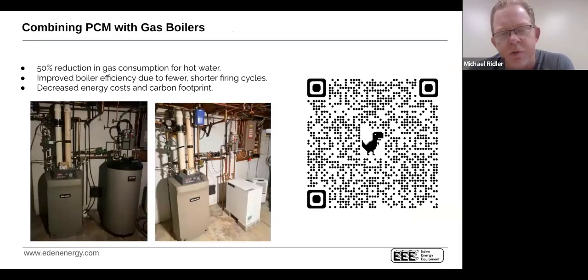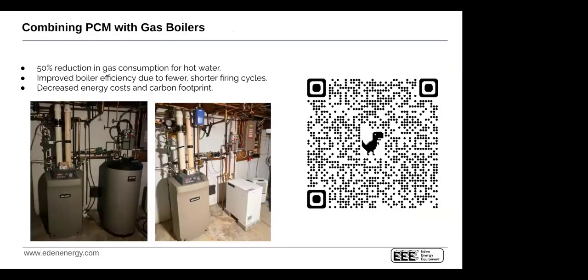I got asked years ago, would you use PCM on a gas boiler? And I was like, I'm not sure that I would. Foolish statement by me. If we can actually install a hot water device that's always condensing and has 50% lower standby losses, it's going to result in a significantly lower gas consumption, which is good, right? If we can use less gas, it's always productive. So NYSERDA did this study. They were able to reduce the gas consumption by 50% simply by taking an indirect out and putting a phase change battery in its place.